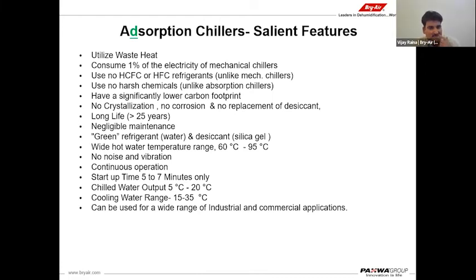In our technology, we don't have any crystallization, no corrosion, and no replacement of desiccant for 25 years since it is a hermetically sealed chiller. Silica gel is filled once in the chiller, and we don't need to open the chiller for any top up or for any analysis of the desiccant. Maintenance is negligible, as we use green refrigerant water and desiccant silica gel. The hot water range is 60 to 95. We can use 60 degrees for chilled water generation for cooling.